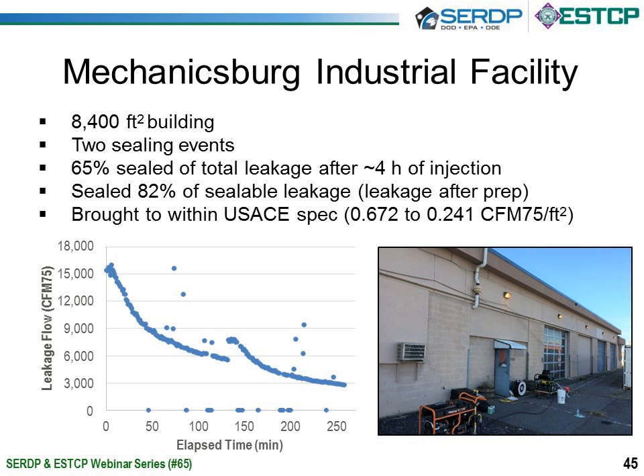The bottom left chart, sealing profile, shows you the process as it worked with respect to time in minutes on the bottom. So it started out about 15,000 CFM at 75 pascals, and we were able to reduce that by about 60% down to 6,000 or so in about 2 hours of injection. We had to pack up for the day and come back the next day. We came back, set up our equipment again, and sealed it further from about 7,500 down to 3,000. So over the 2 events, we were able to seal about 65% of the leakage in a pretty quick amount of time.